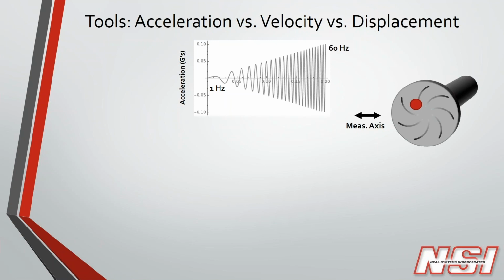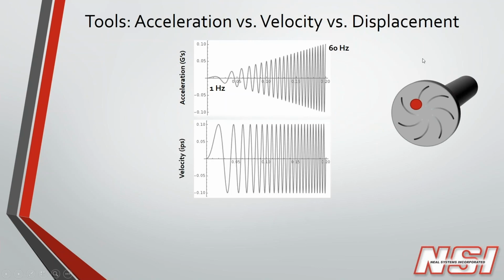So if we wanted to set a threshold in acceleration that we're not comfortable with, where we would want to set an alarm to have our machine get checked or shut it down, we would have a hard time setting that alarm level without knowing the machine speed in this case. So what can we do? Well, one of our options is to integrate that accelerometer signal. And it's interesting, you can see this is sort of data that was made up, but this is a real integration. So you can see at this end, the area under the curve, at the low end, the magnitude of the acceleration doesn't reach very high, but there's a long time for the velocity to build up in the positive or negative direction.